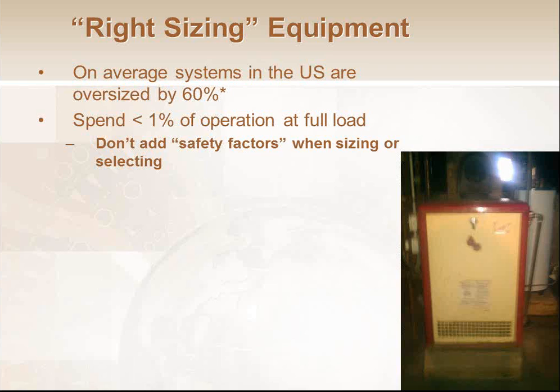Some of the benefits of downsizing it, other than just having a lower first cost, right? If I'm going to buy a 1 million BTU boiler plant or a 500,000 BTU boiler plant, obviously the costs are different. And if I can downsize that plant when I'm upgrading it, I can use that savings to pay for better, more efficient boilers as opposed to paying for bigger, less efficient boilers, if that makes any sense.